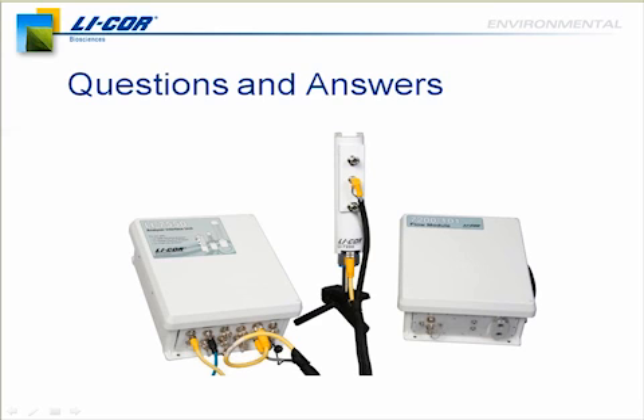With the 7200 now, you can have the fast temperature and pressure, and the benefits of that. So you can use the WPL term, which you wouldn't have with just putting the shroud in there. And finally, if you were to somehow get some contamination or the inside got dirty, and you have a permanently sealed head, then how are you going to open it and get that clean? So you'll run into some troubles there. I hope that answered your question, Katerina.